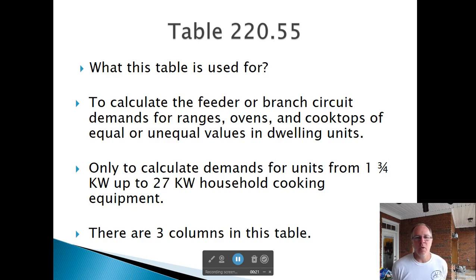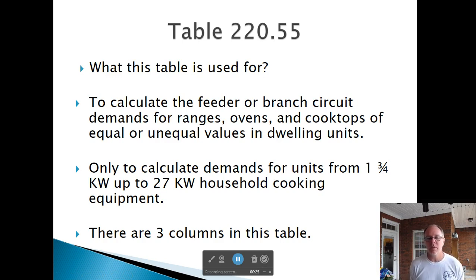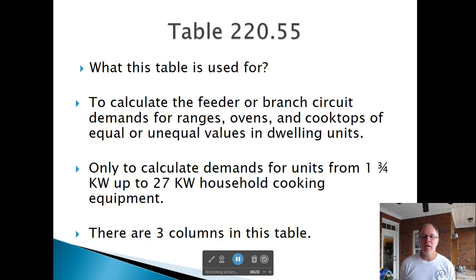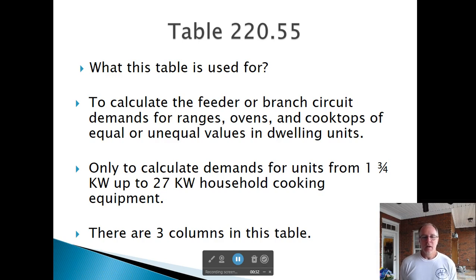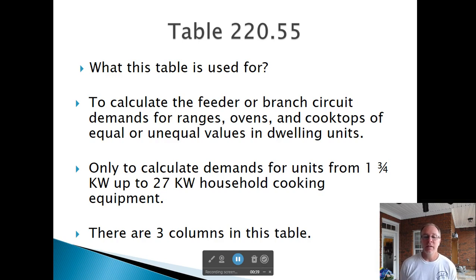Where do we use this table? It's to calculate the feeder or branch circuit demands of ranges, ovens, and cooktops of equal or unequal values in dwelling units. It's only used to calculate demands from units from 1,750 watts up to 27,000 watts.